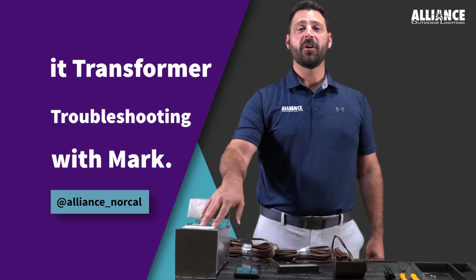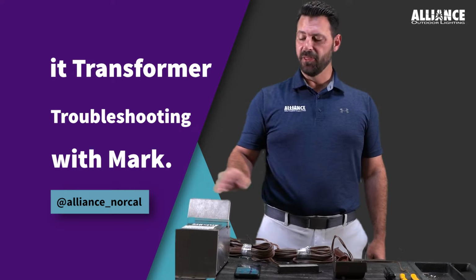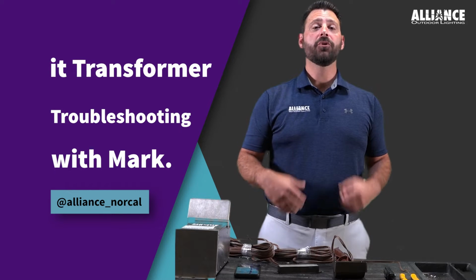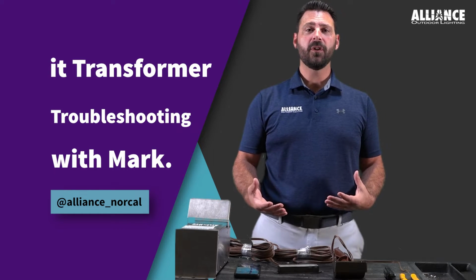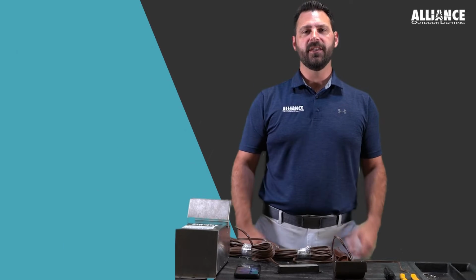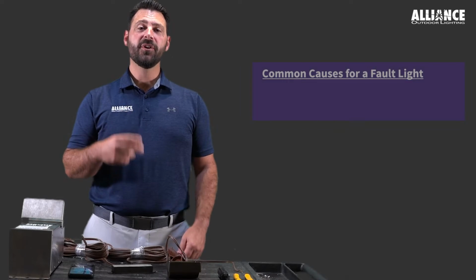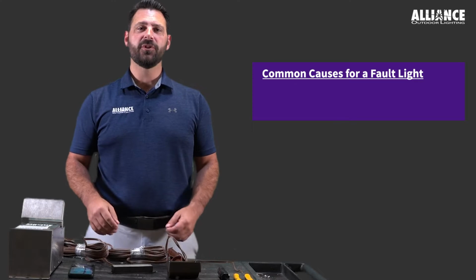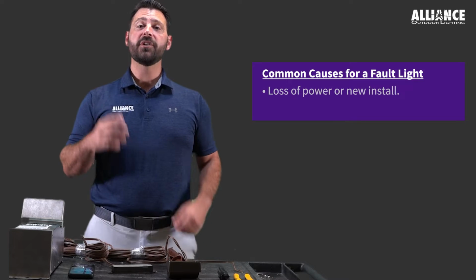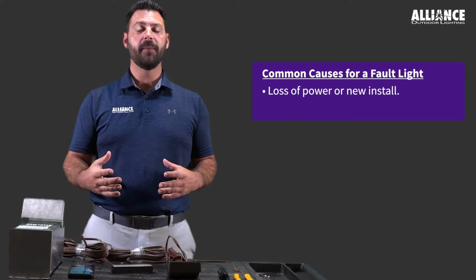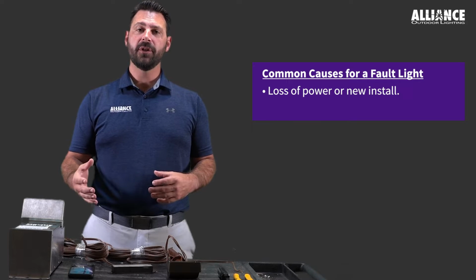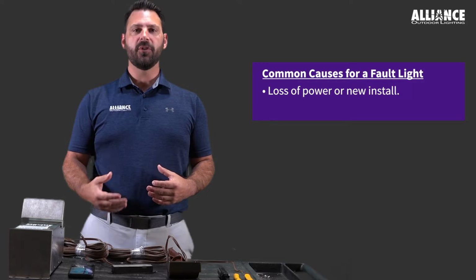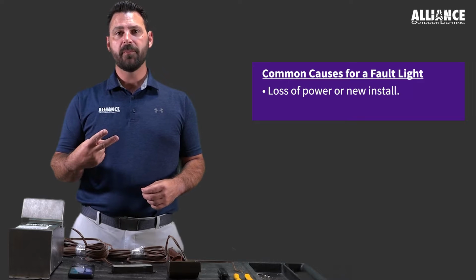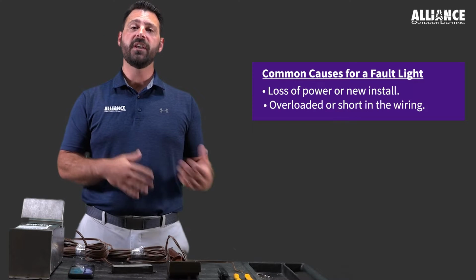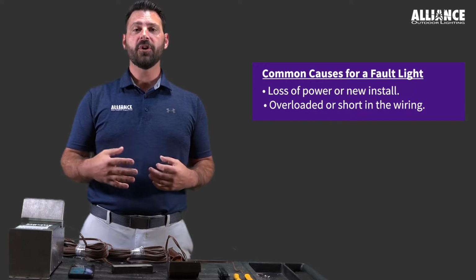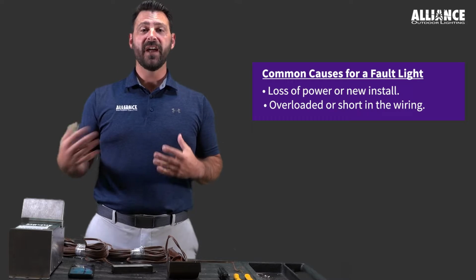Today we're going to be talking about our IT series of transformers and the red fault light that comes on. We'll talk about the most common causes for the red fault light and also how to diagnose that in the field. The two most common reasons that you're going to get the red fault light on the top of this transformer are, one, this transformer has lost power for a period of time. This could be because of a power outage, but it could also be when you first install this out of the box. The second most common reason is there's a short someplace in the field in the wiring. We're going to talk about how to figure out which line that short is on.